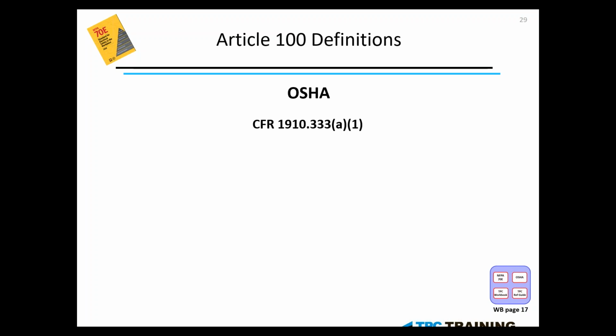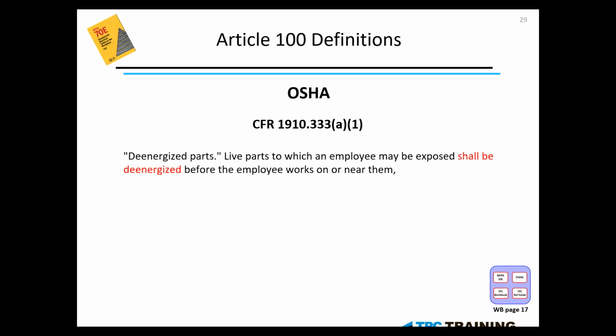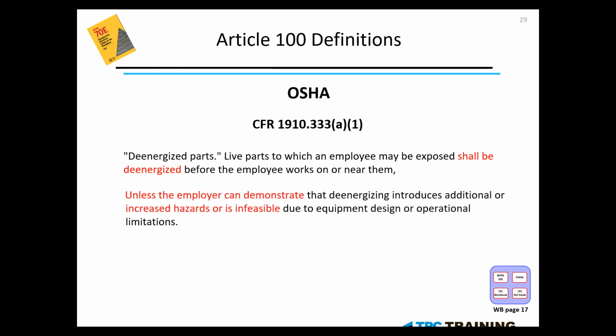Speaking of which, there are 3 instances in which OSHA, Occupational Safety and Health, and the NFPA will allow us to work on energized parts. And it can be found in 1910.333(a)(1). De-energized parts, live parts to which an employee may be exposed shall be de-energized before the employee works on or near them. Now, stress that, on or near them. Unless the employer, it is their responsibility, can demonstrate that de-energizing introduces additional or increased hazards or is infeasible due to equipment design or operational limitations.